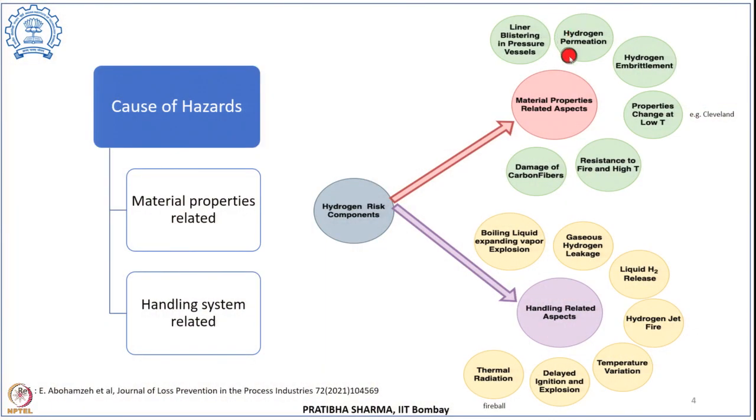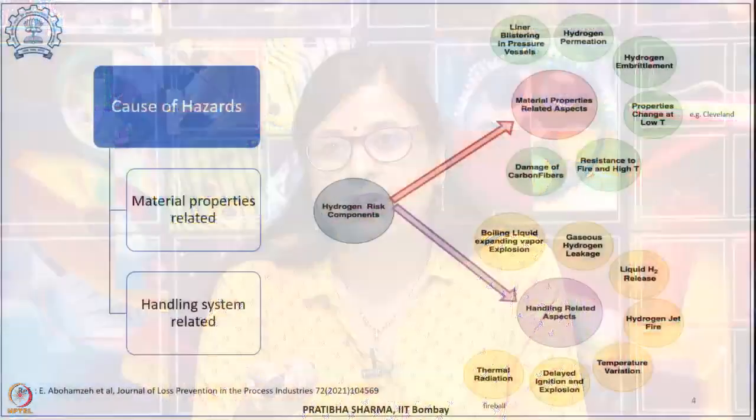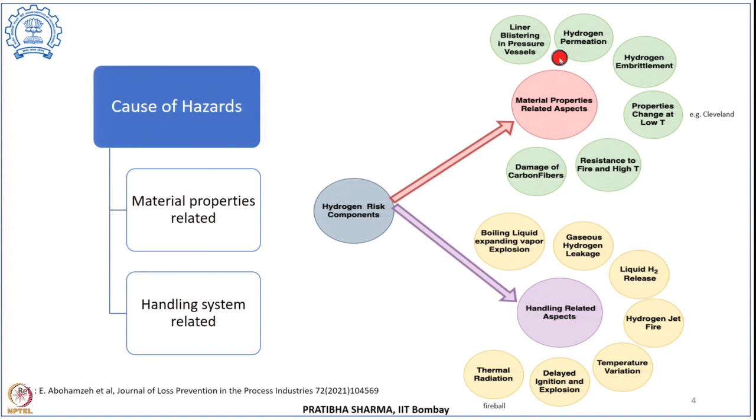Another material property related hazard is hydrogen permeation — defined as the flux or rate of hydrogen migrating into a permeable material in such a way that it can later cause hydrogen embrittlement. Hydrogen is a very small molecule and can migrate through permeable materials. Permeation is insignificant in type 1, type 2, or type 3 containers; however, in type 4 containers it is significant, but it depends upon temperature, pressure, and aging — and as the vessel ages, permeation increases.